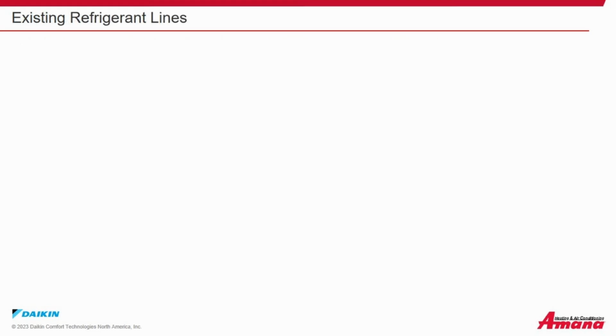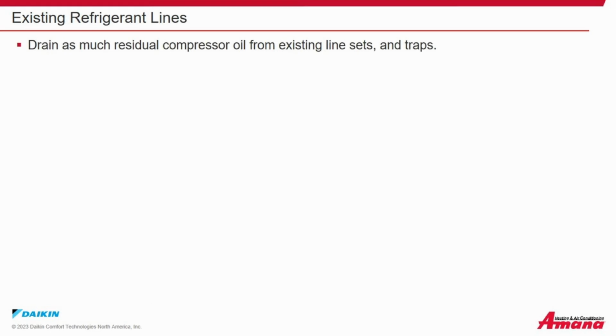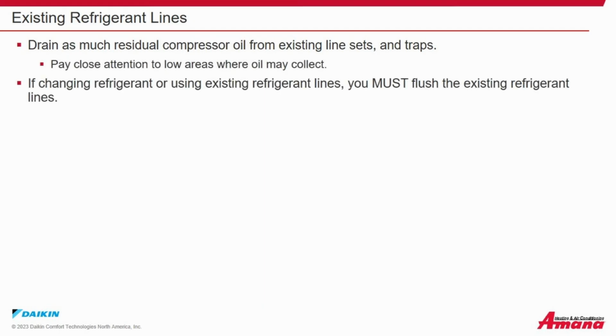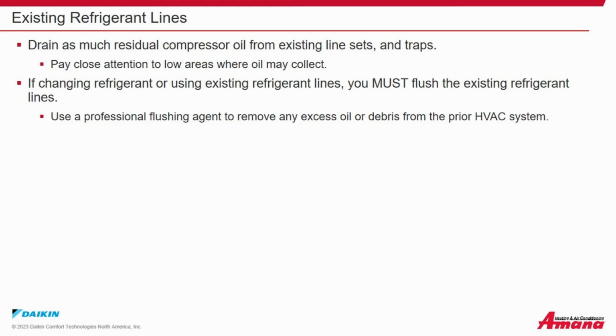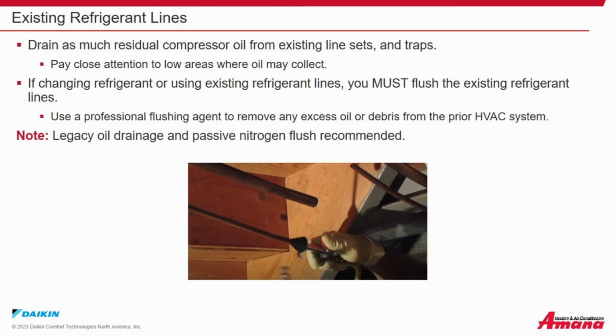Existing refrigerant lines. Drain as much residual compressor oil from existing line sets and traps as possible. Pay close attention to low areas where oil may collect. If changing refrigerant or using existing line sets, you must flush the existing lines. Use a professional flushing agent to remove any excess oil or debris from the prior HVAC system. Note: legacy oil drainage and passive nitrogen flush are recommended.